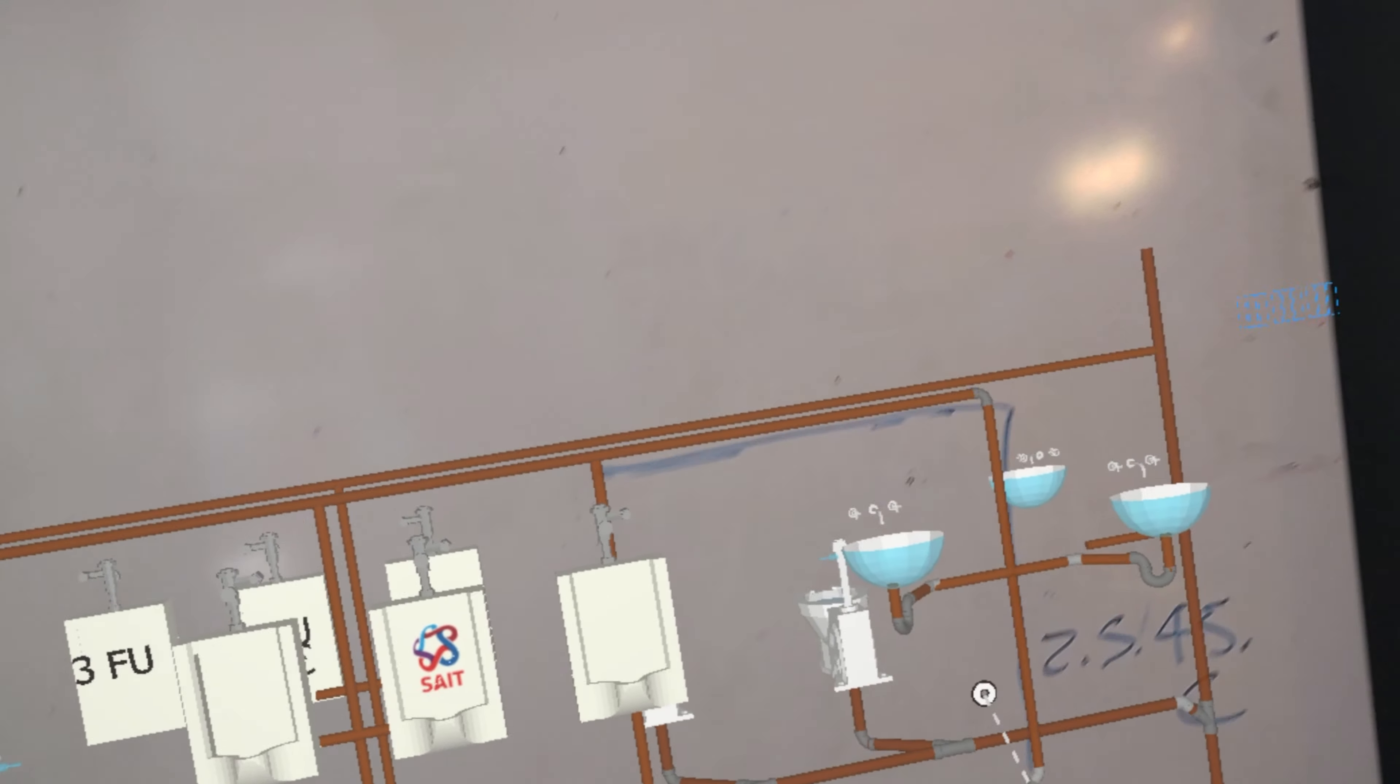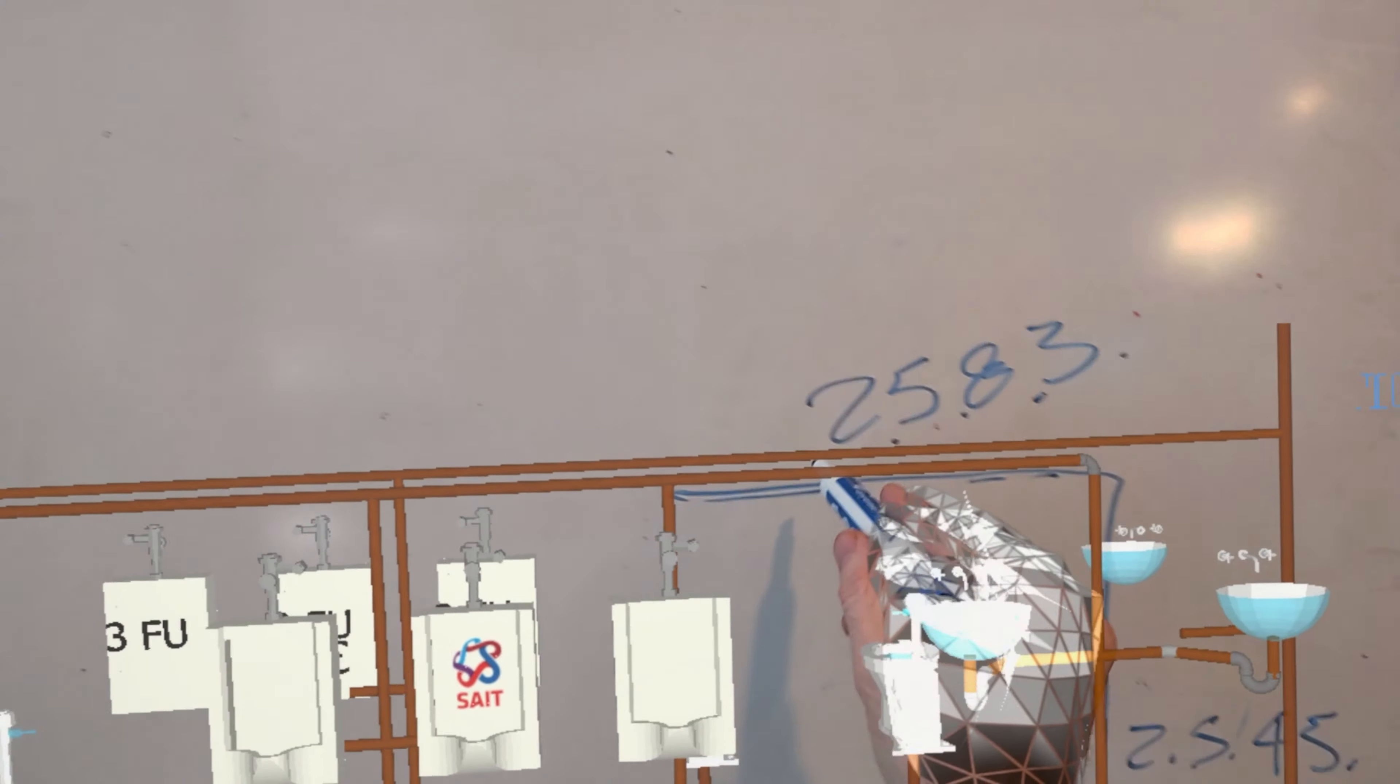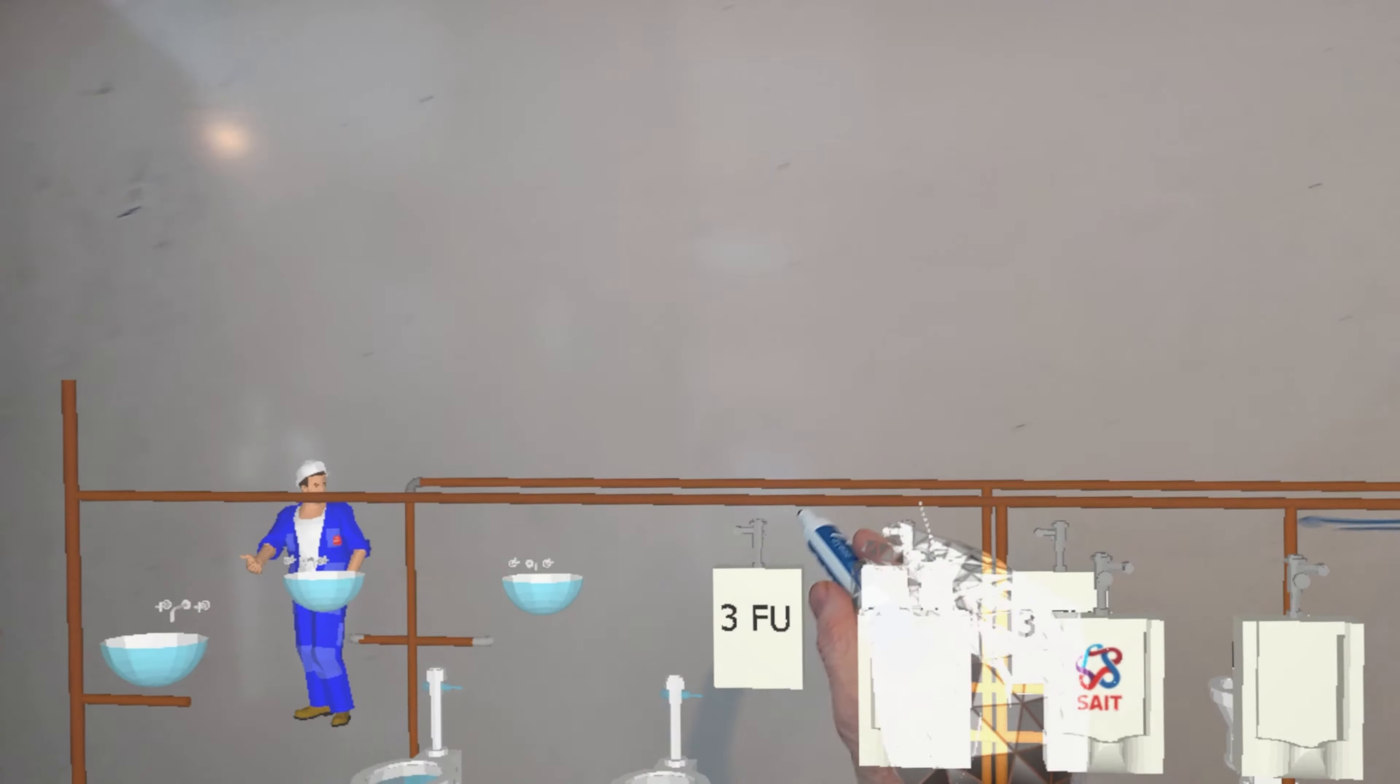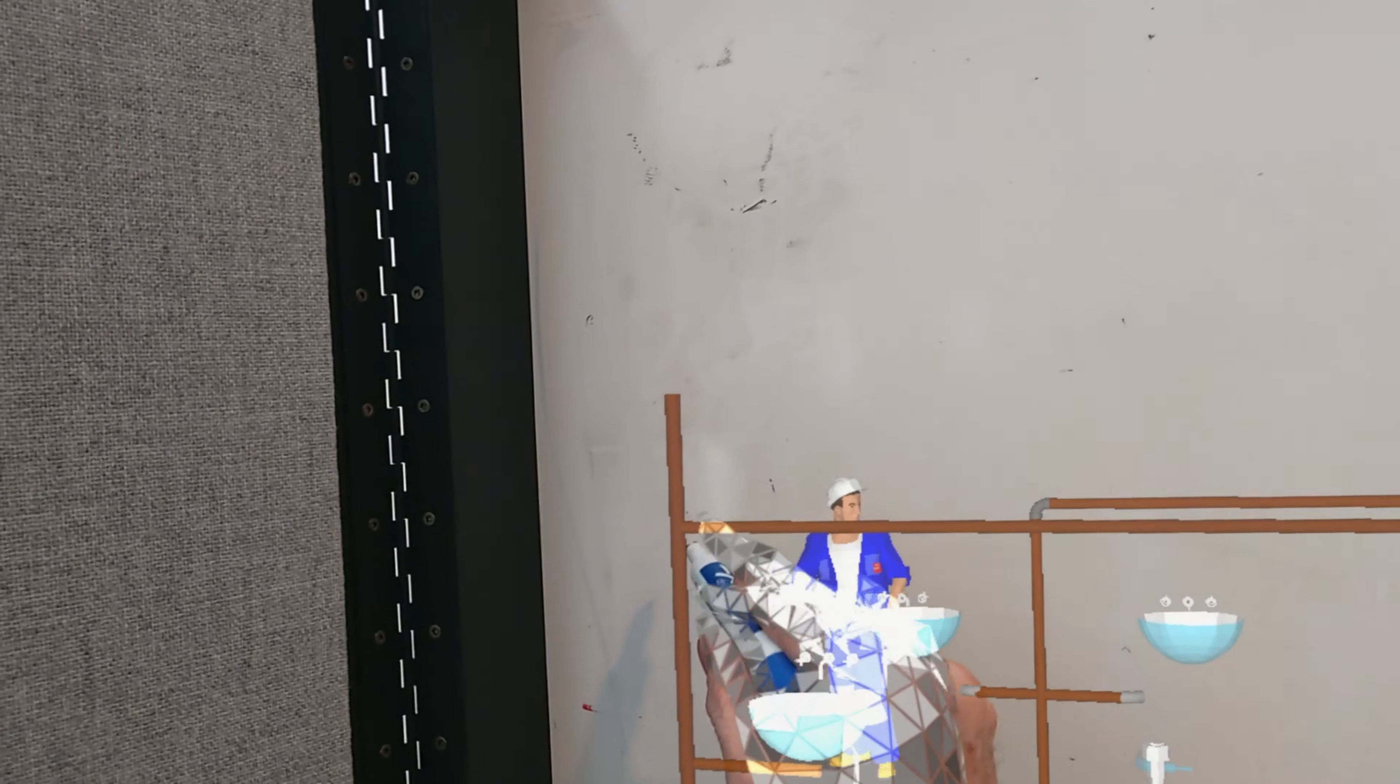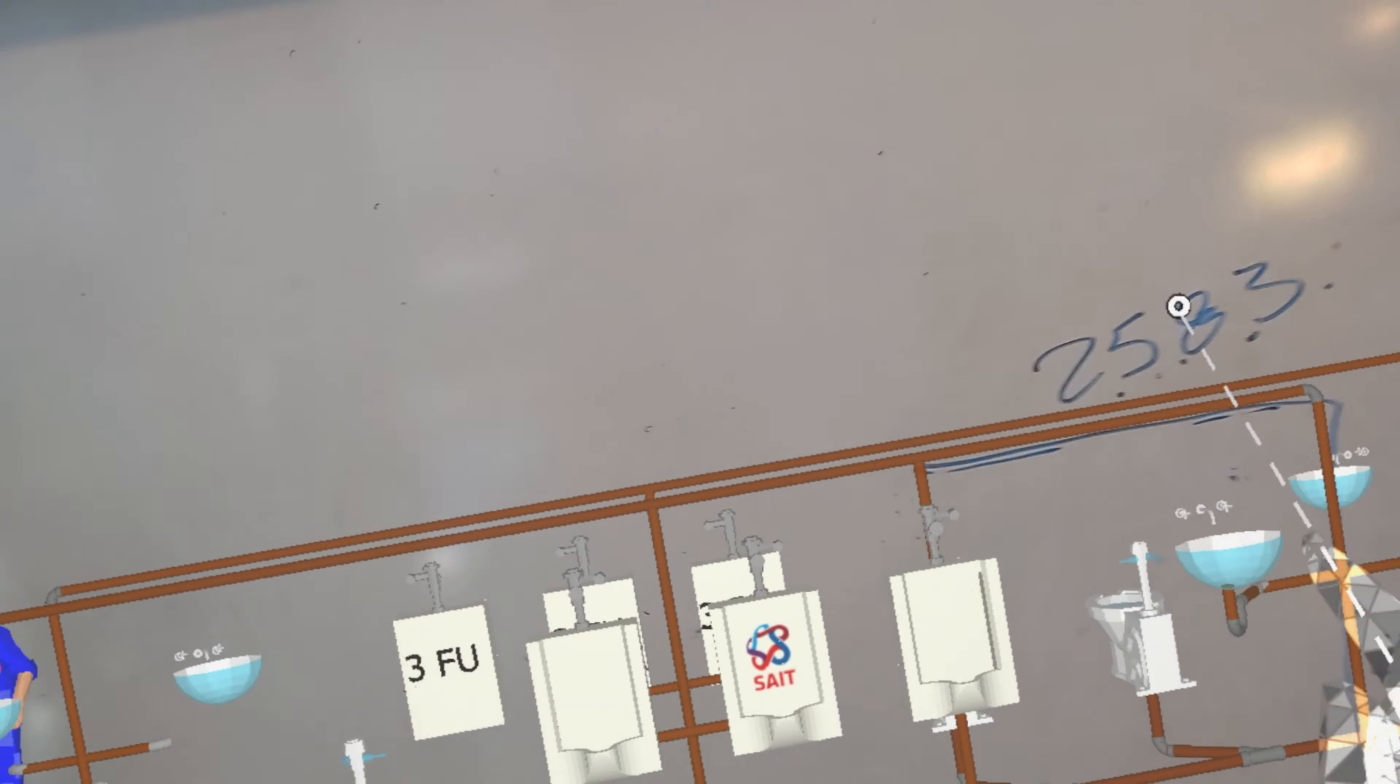And that dry portion of the circuit vent would be sized by 2583. And of course we want our students to measure the developed length. The developed length of a circuit vent is from the horizontal soil or waste pipe connection to the stack vent header or outside air. In this case it would be to outside air. So they would have to measure this in meters to find out the size of this circuit vent.